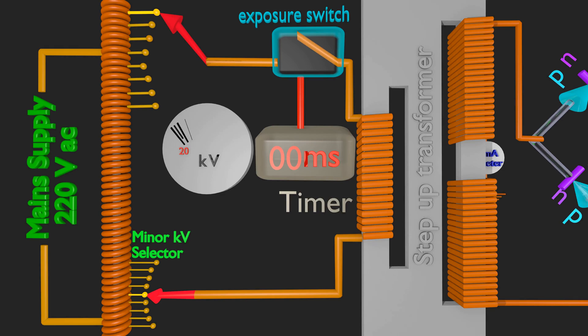A voltmeter called prereading kVp meter is placed at primary of high-tension transformer. But it is calibrated to show voltage across X-ray tube during exposure.